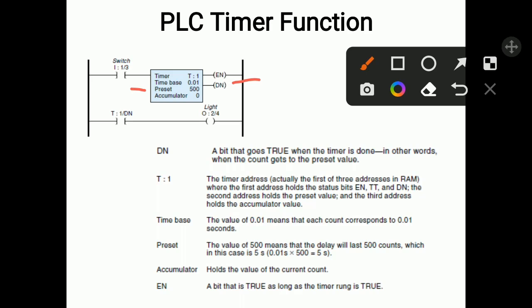Next, T4:1 is the timer address. It consists of three addresses in RAM: the first holds the status bits of EN, TT, and DN; it also holds the preset value as well as the accumulated value. So all three values are held by this timer address.